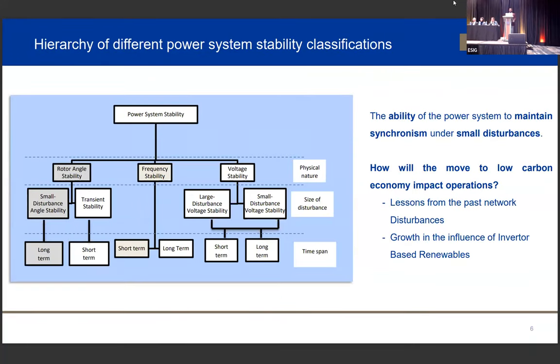So why are we here? I'm just going to give you the brief. The hierarchy of power system stability classification normally has three types: voltage stability, frequency stability, and rotor angle stability. First one, voltage: we don't have problems in South Africa. We can manage that. Normally, if it happens, it's local within the network. Frequency stability: because we have a lot of trips and a lot of load rotations, frequency goes up and down a lot, but it's manageable. The challenge is the rotor angle stability. That's the focus of my presentation today.